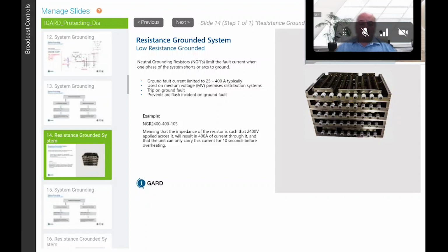We limit the fault current to 400 amps for 10 seconds. With a low resistance grounded system, you must have a time duration. That time duration is 5 seconds, 10 seconds, 60 seconds, extended time, or an hour. So your typical ground fault current is 25 to 400 amps.